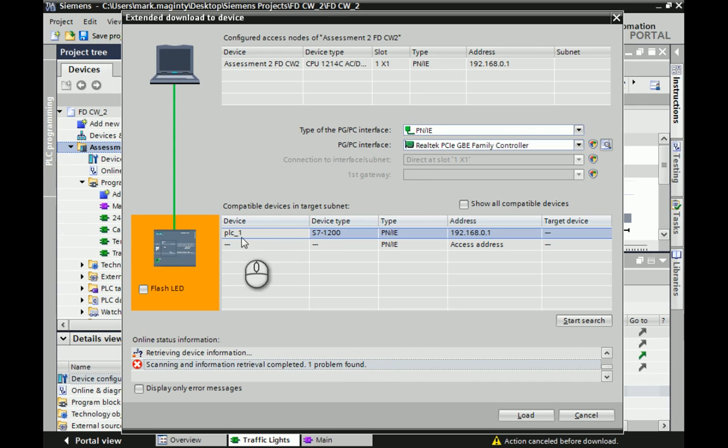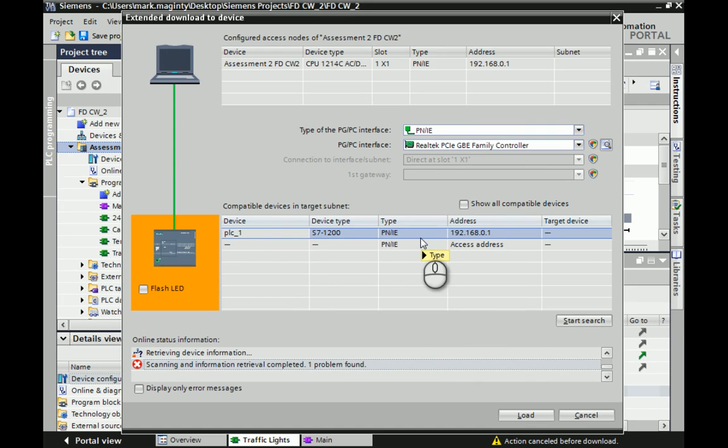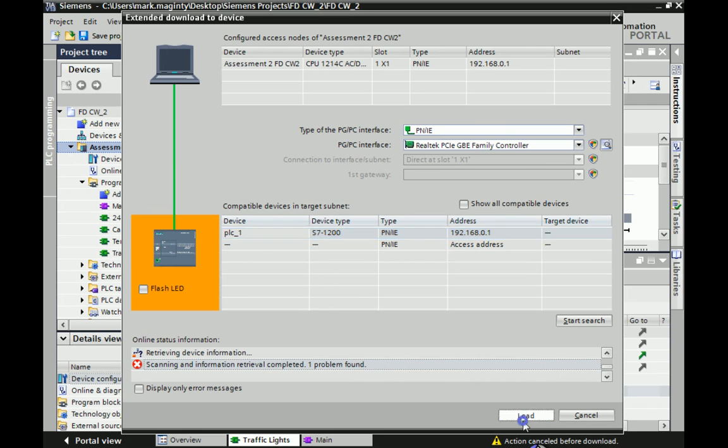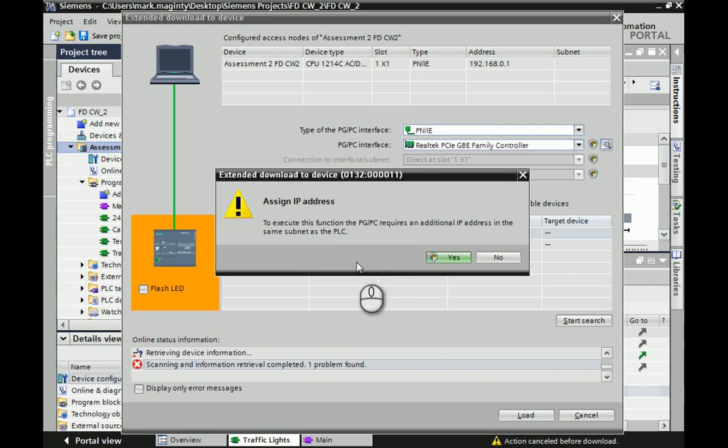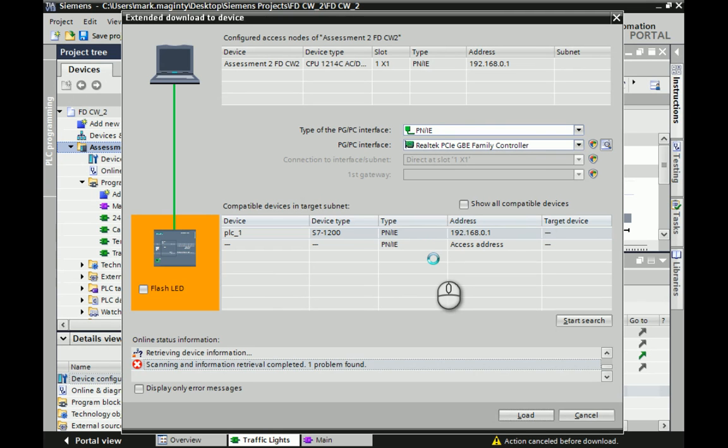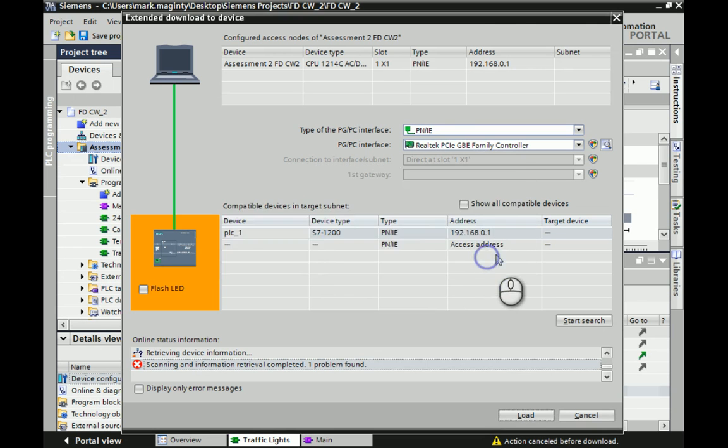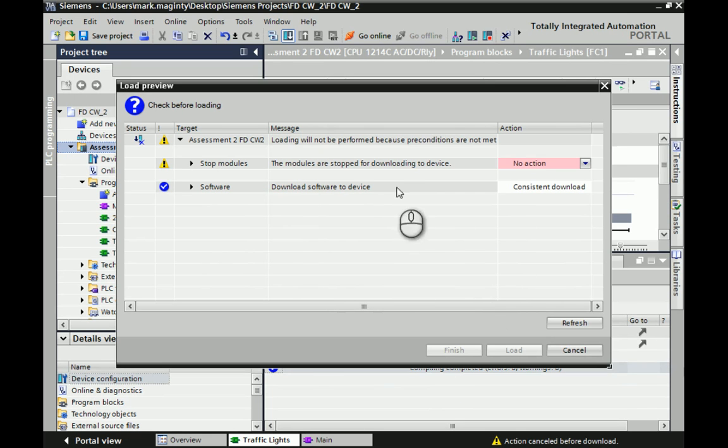Once we have the PLC outlined, it should find the PLC via the cable, as long as you have it connected to your laptop or desktop and to the PLC and powered up. We've run through the Start Search option. It's come up with the one PLC it found at the end of the cable. Then we should be able to hit Load. Depending on if this is your first time connecting or a second or third time, you get different messages. This one here asks that you assign an IP address. Just hit Yes to assign it with an IP address. It'll take a few seconds to load and tell you that it was added, which we're not overly too concerned about.